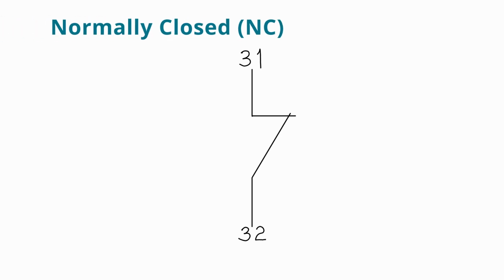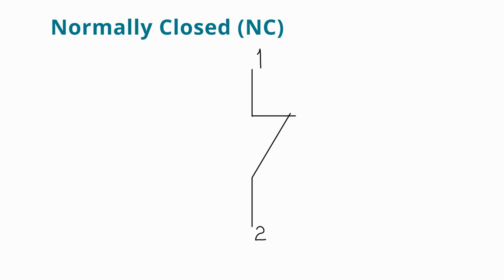And then normally closed contacts are closed in the default state. They open when the device is activated, interrupting the flow of current. They are labeled with any combination of numbers where the least significant numbers are 1 and 2. For example, they could be labeled 1 and 2, or 11 and 12, or 21 and 22, and so on, as long as the last numbers are 1 and 2. Now, the only normally closed contacts which are labeled differently are the ones on a traditional overload, which are labeled 95 and 96. The stop button and the emergency stop buttons that we use in direct online circuits are normally closed contacts. In a simple non-reversing direct online starter, devices with normally closed contacts are wired in series with the control circuit.